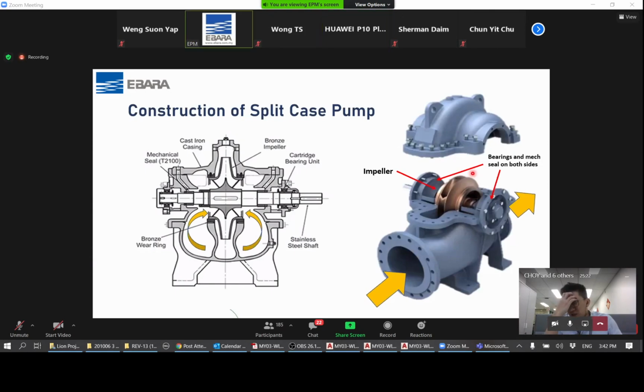So it's usually used, like I mentioned earlier, for bigger flow applications like centralized air conditioning systems, pumping large amounts of chilled water through the chillers. And in such a case, the flow rate is always more than, let's say, 2 to 300 meter cube an hour. And even in some district cooling systems. So again, coming to the construction of the pump, it is a very robust pump, with a very durable construction.